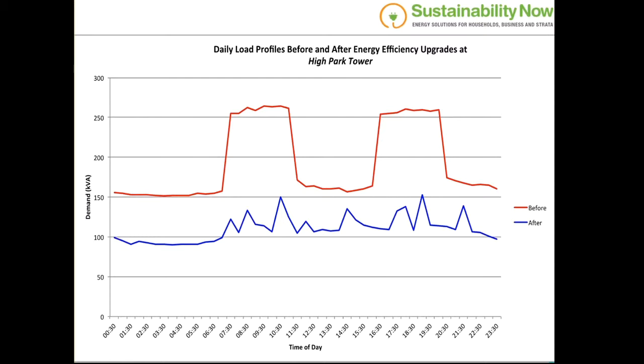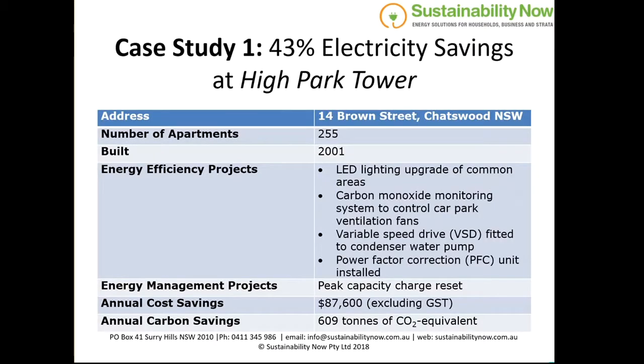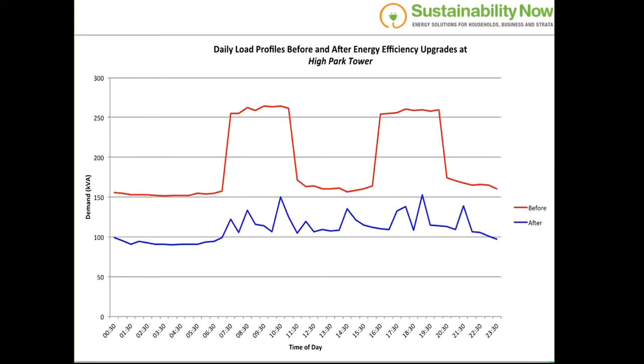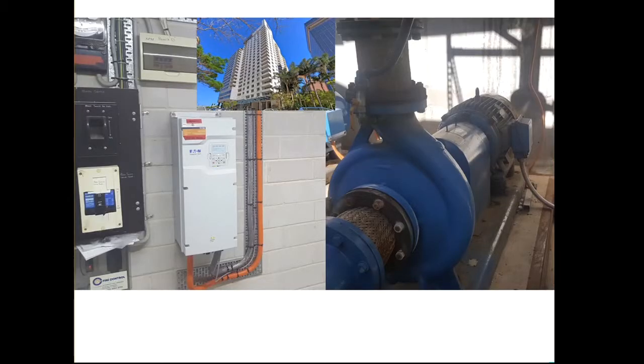They also put a variable speed drive on their condenser water pump, and a power factor correction unit. We reset the peak capacity charge after we did all this, and as of last year, they were saving $87,600 in electricity and lots and lots of tonnes of CO2 equivalent. So that's what their load profiles changed to - there's the condenser water pump and the variable speed drive on that. Made some good savings as well.